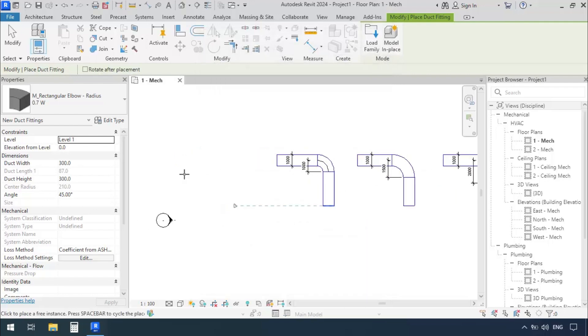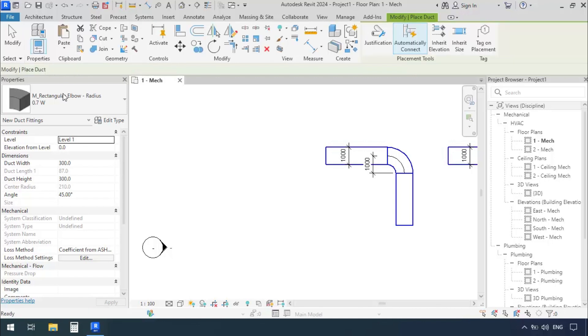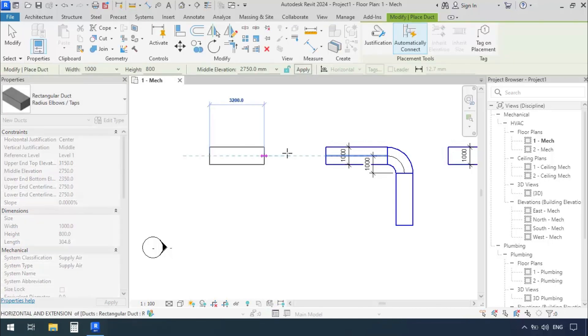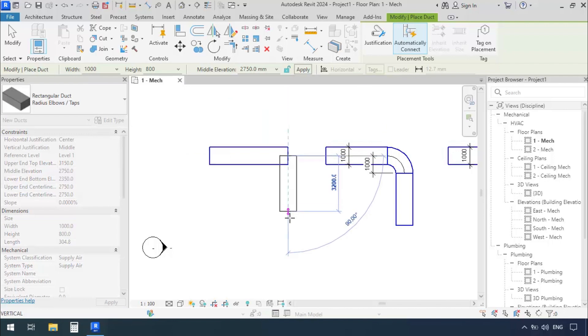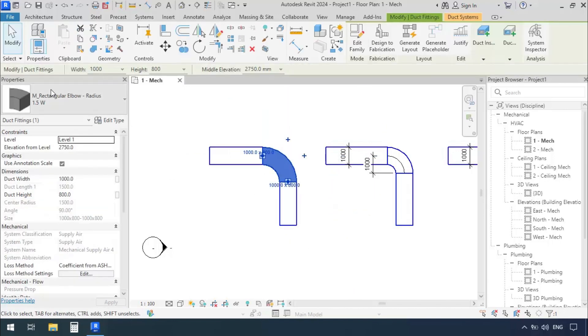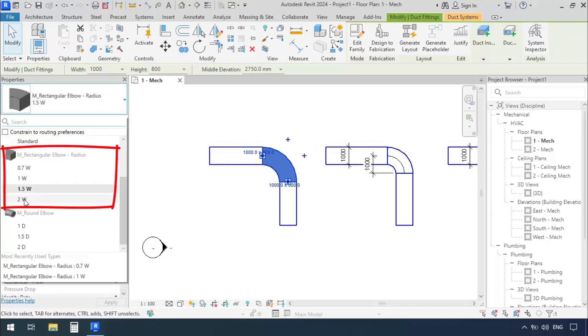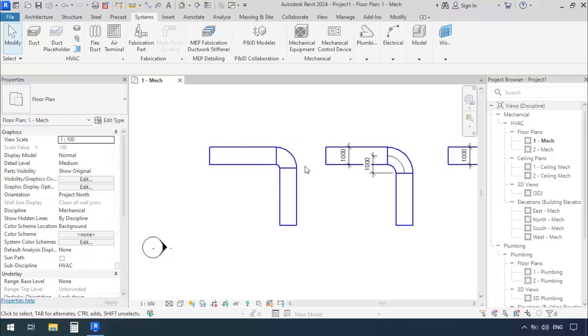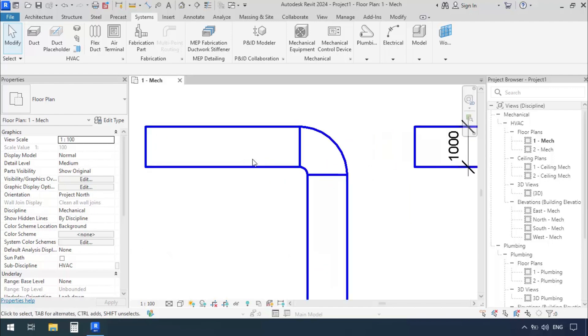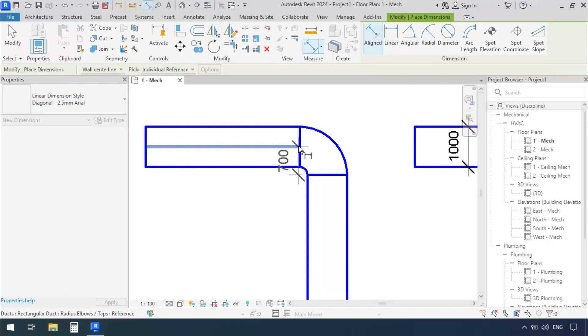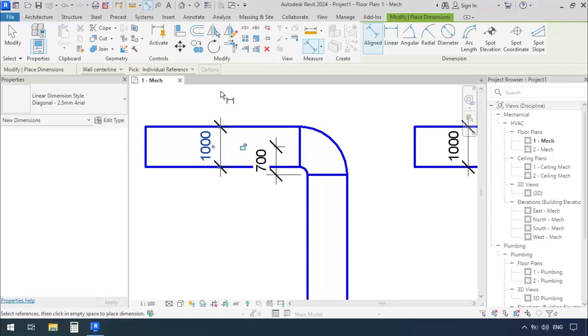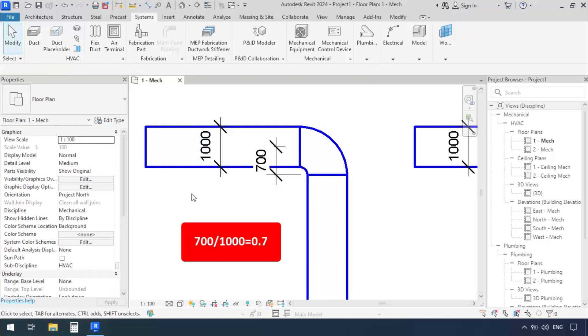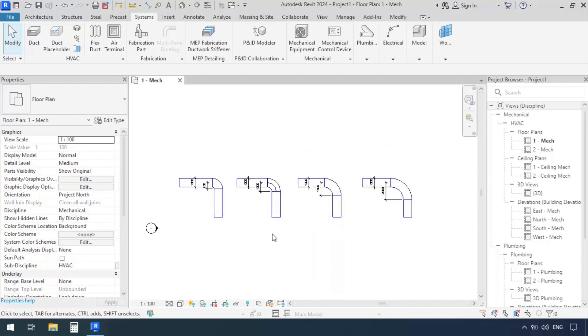We'll go to the Systems tab and click on the Duct command. With Width 1000, we'll draw another duct and press Escape. Now we'll select the Elbow. In the Properties window we see the ones we had by default, plus this 0.7 we just added. This one's radius is much smaller than the others. We can measure it to make sure. Click here and then here, then somewhere empty. The Width is also 1000. So 700 divided by 1000 equals 0.7, or in other words, 0.7W.